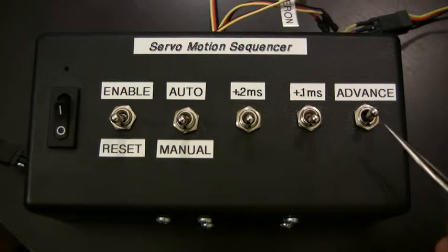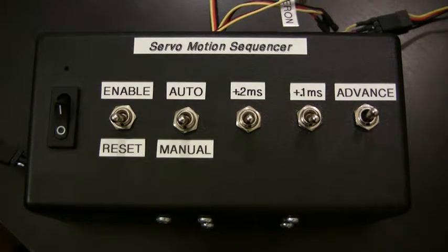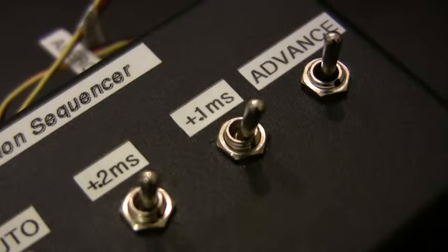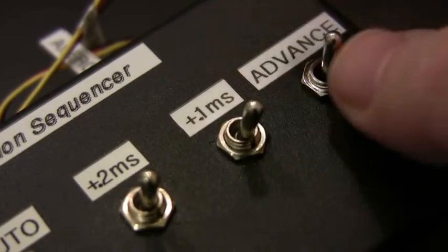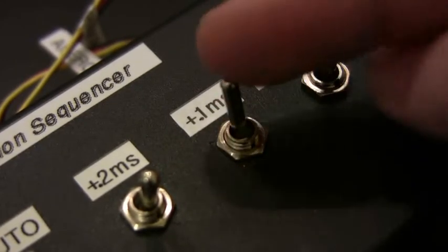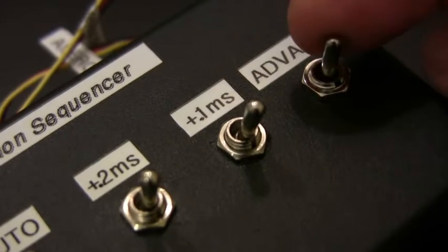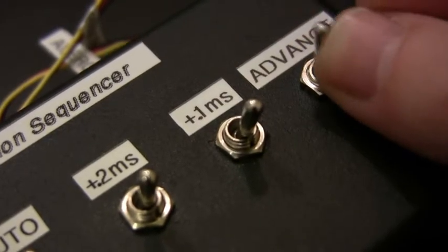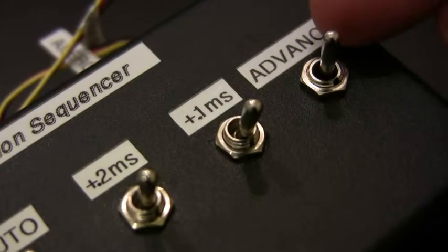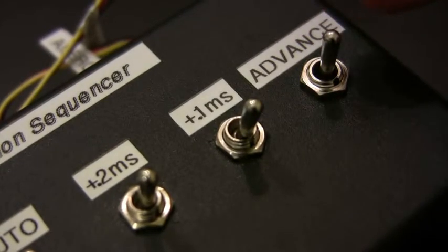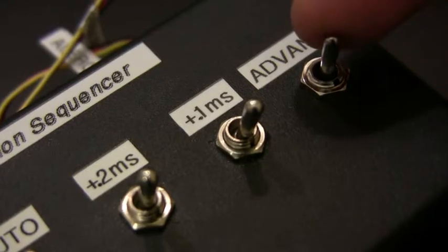And this is a momentary switch that is used in manual mode to advance the servo whenever the user is ready for the next test sequence. It's worth noting that there are two types of switches. One is a latching switch which will move and stay in each direction, and the other is a momentary switch which moves away from neutral to the on position and then back to neutral. In this case the advance one is the only momentary switch. All the other ones are latching toggle switches.